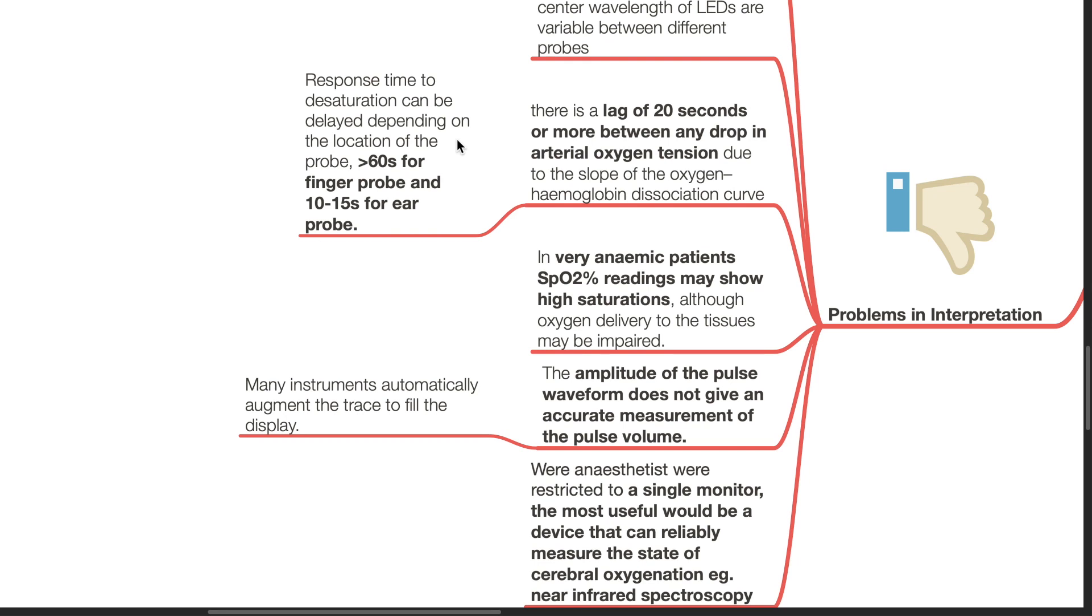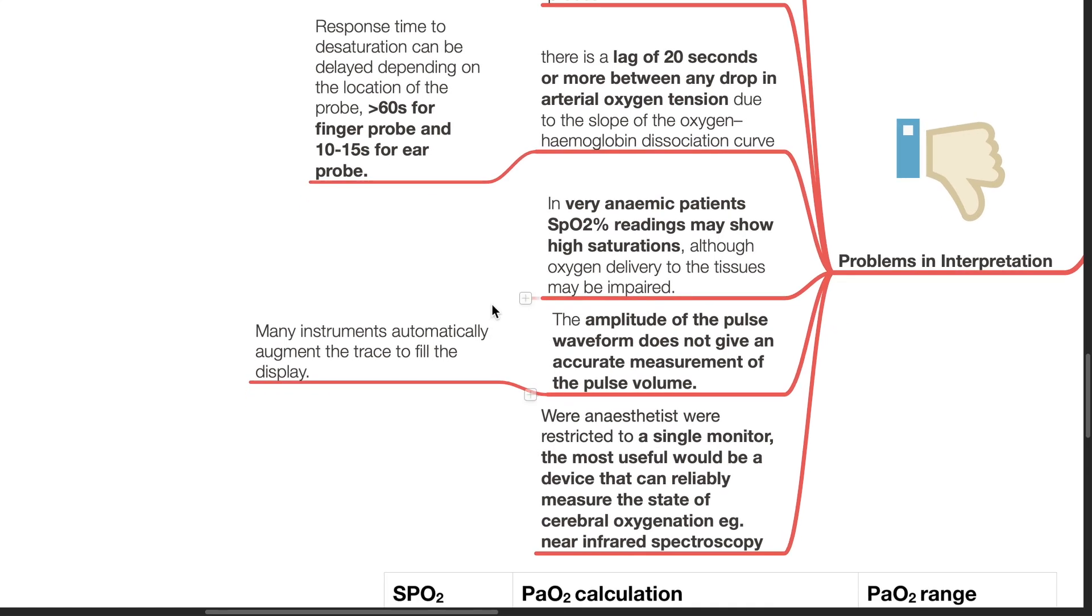In very anemic patients, SpO2 readings may show high saturations, although oxygen delivery to the tissues may be impaired. The amplitude of the pulse waveform does not give an accurate measurement of the pulse volume as many instruments automatically augment the trace to fill the display.